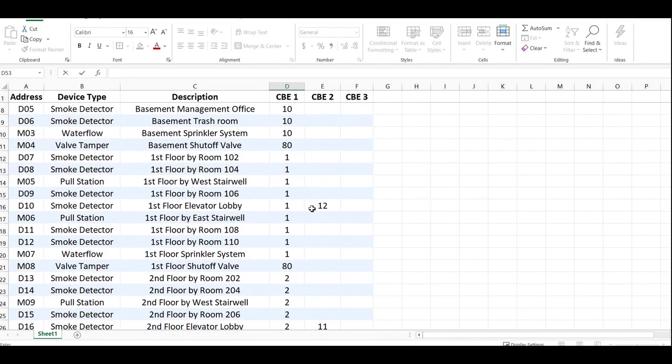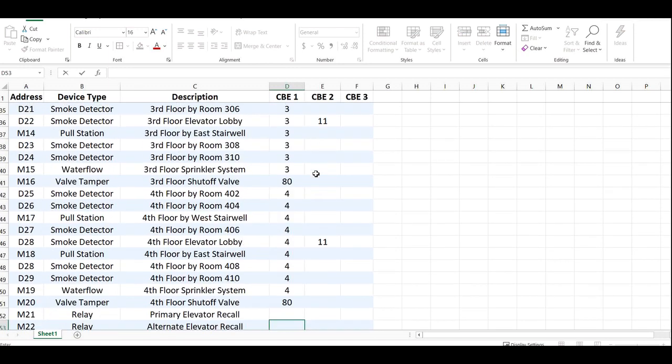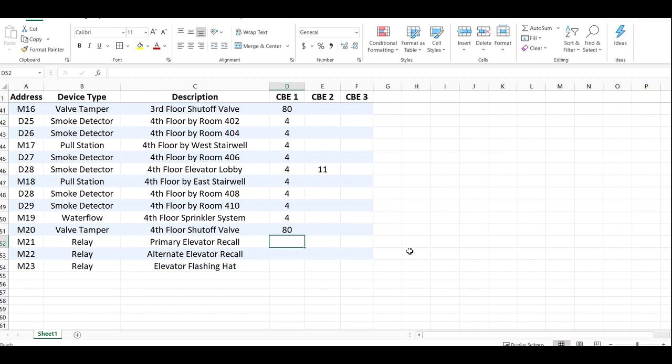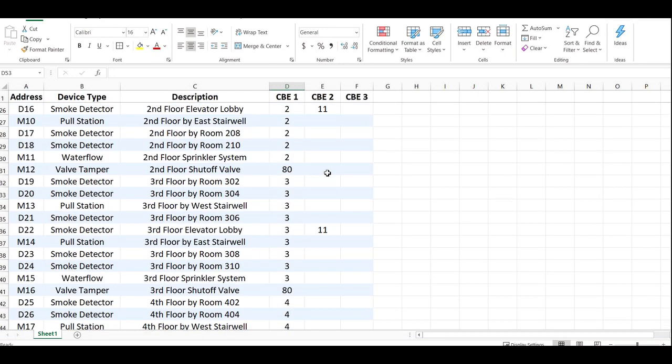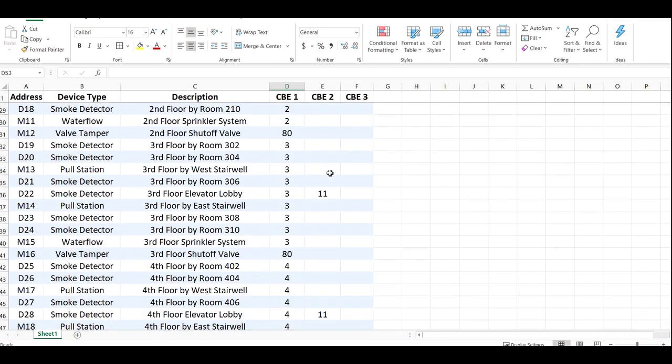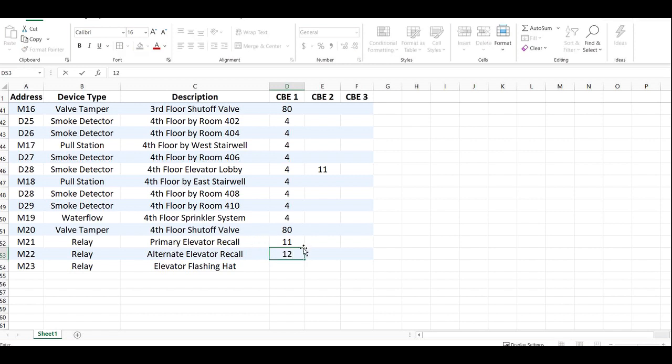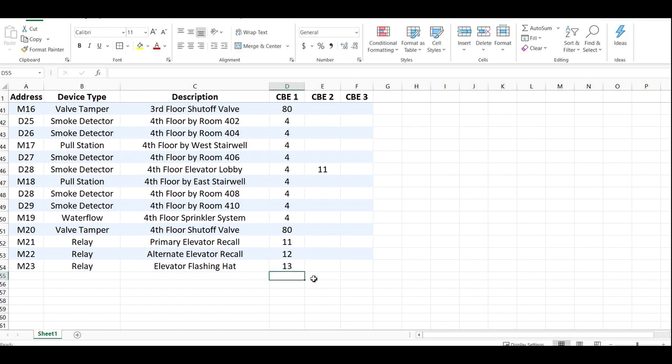And we decided that was zone 11. So if this is a Fire-Lite panel or a Notifier panel, we're just going to give this zone 11. So now when any of the, when zone 11 on the input side activates, zone 11 on the output side is going to activate and that relay is going to change states. Elevator recall, I'm sorry, alternate recall is going to be zone 12. And for flashing hat, this is when you need to know, this one's going to be 13.